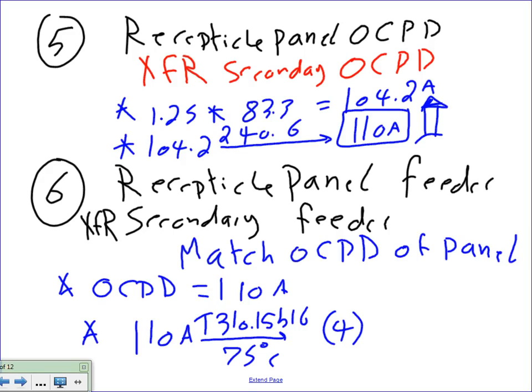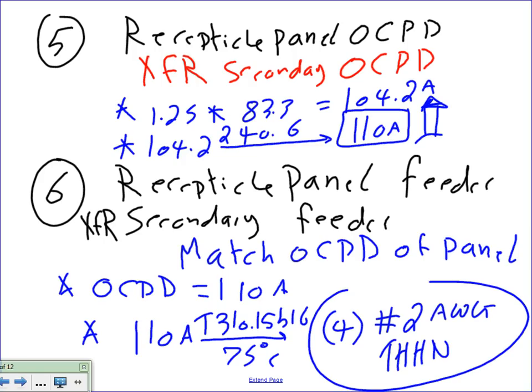What's the size? Number 2. Do I have a second? Second, okay. Number 2 AWG THHN. And if you need to find the conduit, you get smart and you find the conduit for it. Done. Here's the conductor on the secondary side. The secondary conductors, secondary transformer, secondary conductors, or the panel feeder, right?